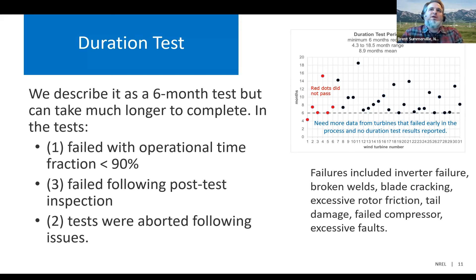So after the study, we decided to change the 10-minute averaging interval, which was unique to duration testing, to 1-minute averaging. This means your whole test setup is utilizing 1-minute averaging on your sample data, which makes things more optimized. And we require the turbine to demonstrate reliable operation through 10 hours of wind speeds of 15 meters per second and above. So it needs to see some time in high winds, and then overall 1,000 hours of power production.